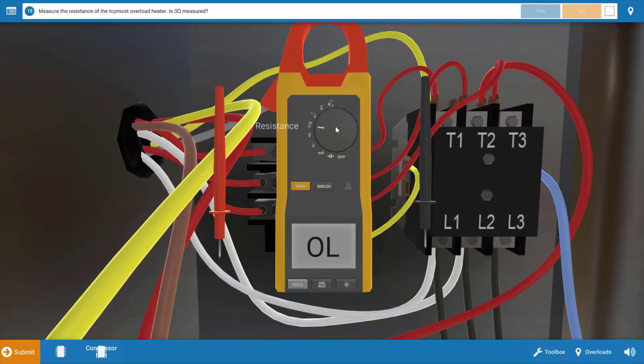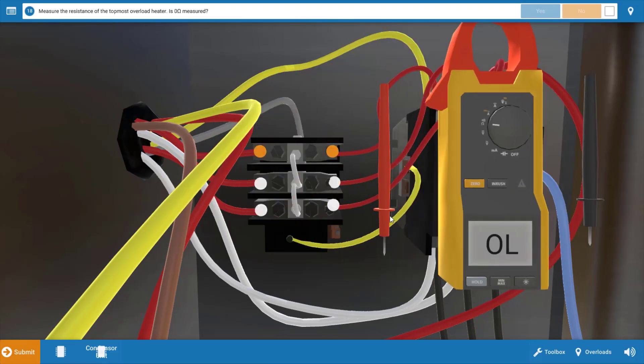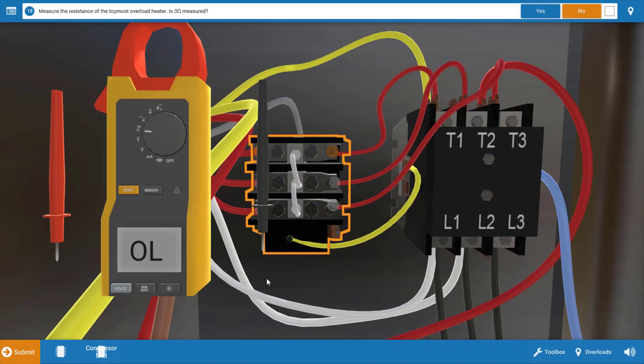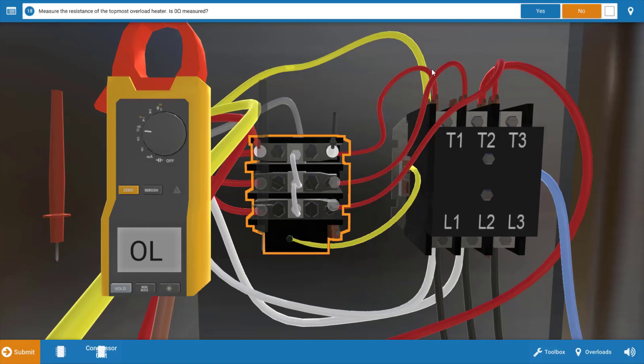Click okay after you've turned the power off, and we'll start by measuring resistance of each of these heaters. Starting with heater number one at the top. When we measure resistance of the heaters, they should read about a half an ohm or so. When we place the leads across the heater, we measure OL or infinite resistance on the meter, and this verifies that this particular heater on the top is open. This is going to break line one going to the compressor. Again, it's going to try to start on the other two legs with single phase power, draw locked rotor amperage, heat up the other heaters, and trip one of the overloads, which is going to break power to the contactor coil.